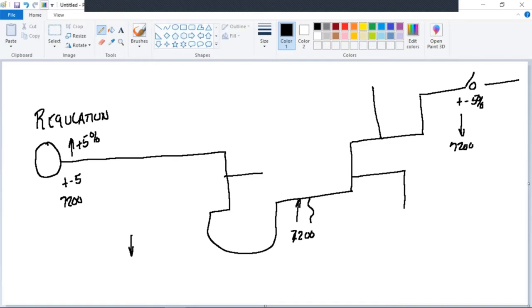All right. It warms up to a nice 72 degree day. Everybody's left the house. They're at the office doing their work. What do you think the voltage is going to do? It's going to rise. So what do I need to do to it? Lower it at the substation. All right, I need to keep it within plus or minus 5%. That's the purpose of a voltage regulator on your system.